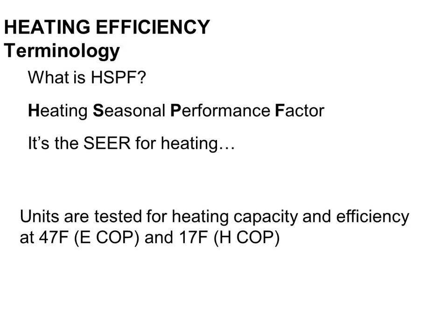Like I mentioned, HSPF is Heating Seasonal Performance Factor. It's very similar to the SEER test, but it's for the heating side of the equation. The SEER test is done at 95 degrees outside. The HSPF is done at 47 degrees outside. Sounds kind of like an oddball number, but the reason it evolved that way decades ago is that 47 outside from the typical indoor design temperature was the same delta T as 95 to the typical indoor temperature on a cooling system. So 47 is kind of the opposite of 95 in the heating world, if you will.